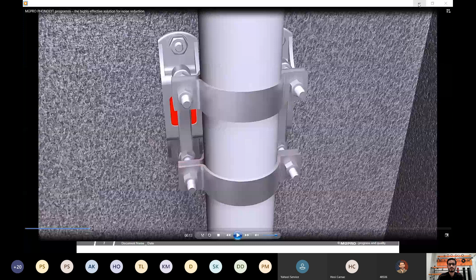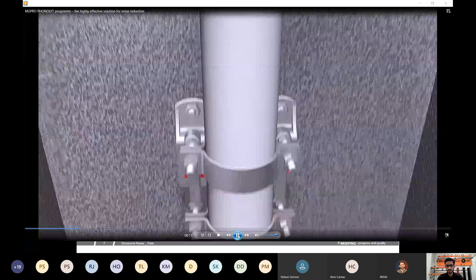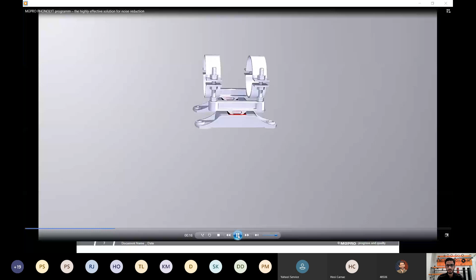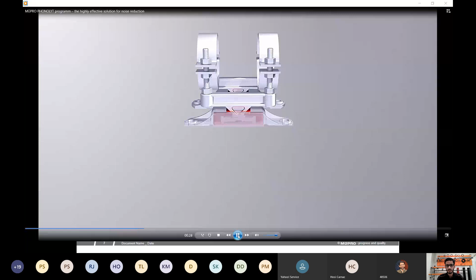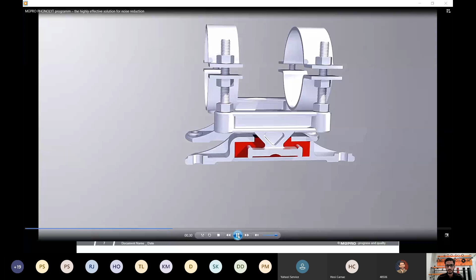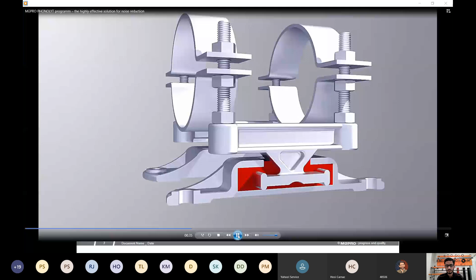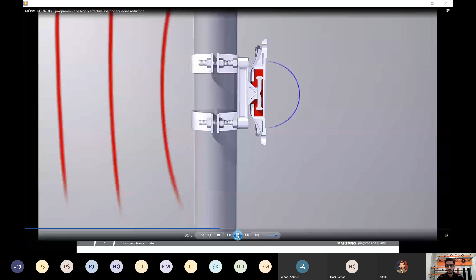Mupro has developed the Phonolyt range for effective vibration control. The Phonolyt system components interrupt sound bridges between the source of vibration and the building structure. The sound-decoupled Phonolyt fixed anchor point for pipelines allows significant reductions in structure-borne noise to be achieved. The functional principle, the low sound input surface of the sound decoupler, and the vulcanized, highly elastic Muprolan absorb the structure-borne noise. The decoupling effect is further enhanced by the small egress surface at the foot of the building structure.